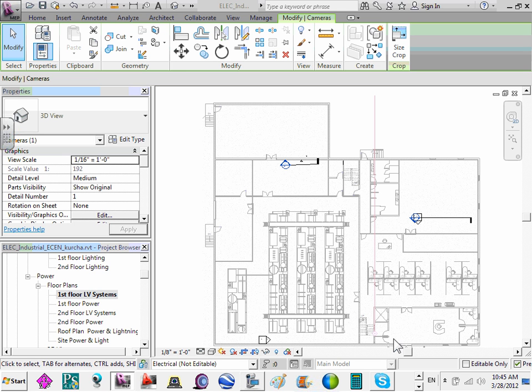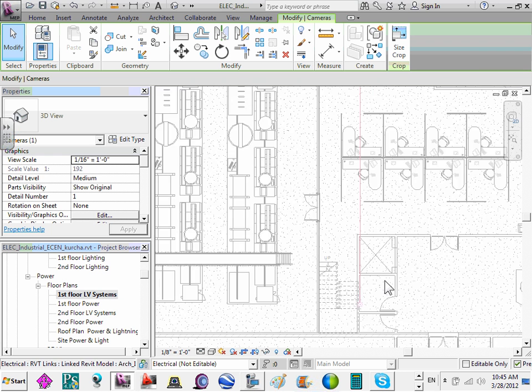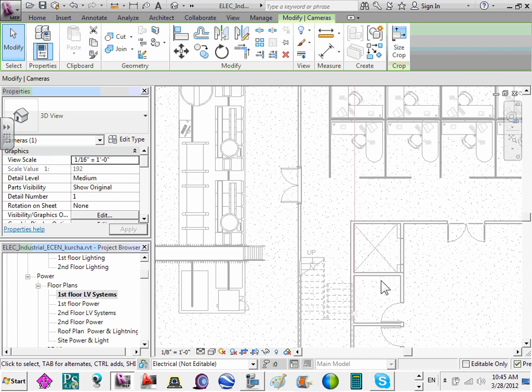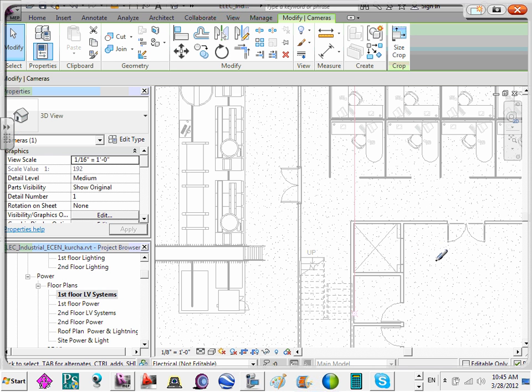Okay, so we talked about flows and tampers, so let's talk about what else is required. Got an elevator here, so we're going to have to put smoke detection in each elevator, in each lobby. Depending if they have a damper up on top, we used to have a smoke detector up on top, but typically that's not required. You're going to have a smoke detector in the elevator machine room, which I assume is the elevator machine room here.